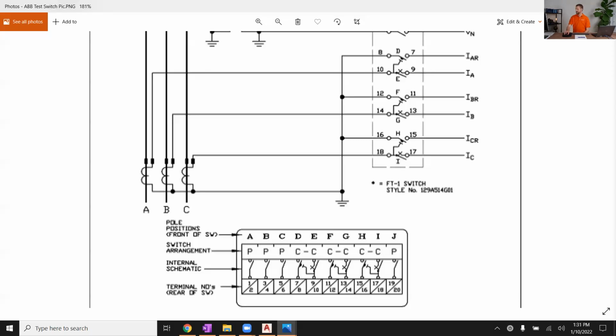Can you show one example hand drawing showing CT connected to the test switch? Yes, I will do that in just a moment. Let me see if there's any others I can address quickly. Omicron is a favorite test kit. I'm glad you have some experience with that. Opening just one current could possibly cause a false ground trip. So yeah, it's not good practice to open just one, but you're going to try to open them both fairly quickly to one another.